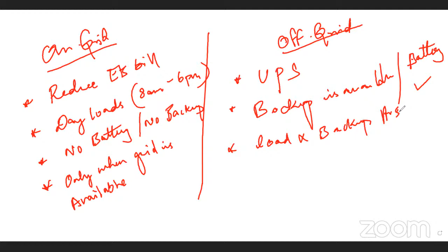Because most of the people who sell the off-grid plant tell that it is a 5 kilowatt plant, but that doesn't mean that 5 kilowatt plant gives backup for 12 hours — it may give for 2 hours also. That completely depends on the load and the number of hours the load has been used under the backup condition. So that eventually, or directly, refers to the number of batteries required for the system. If the number of batteries is more, then the backup hours will be more; if the number of batteries is less, then the backup hours will be less. So that is the main objective of off-grid system.